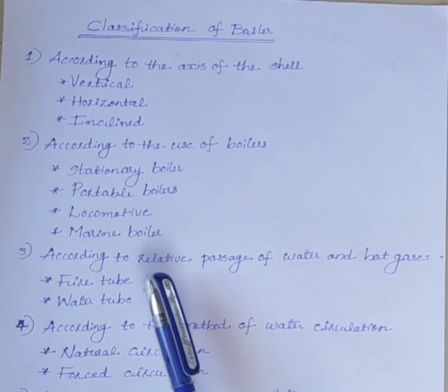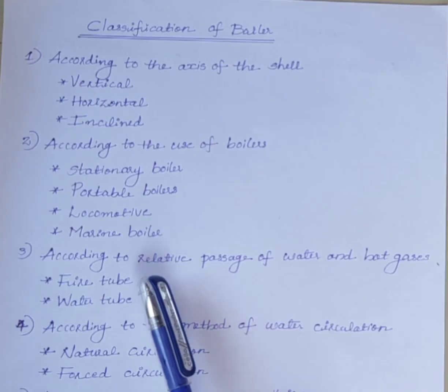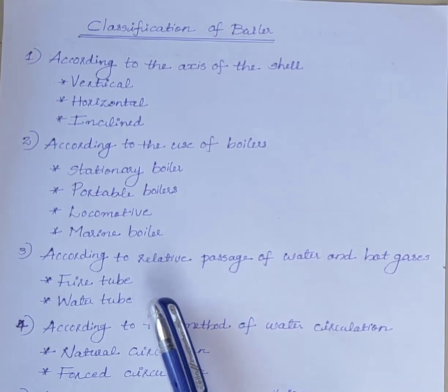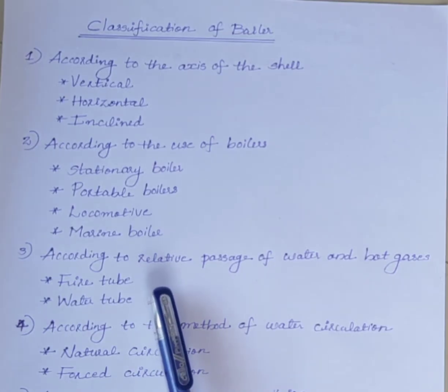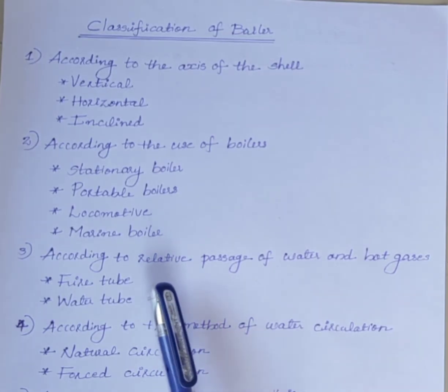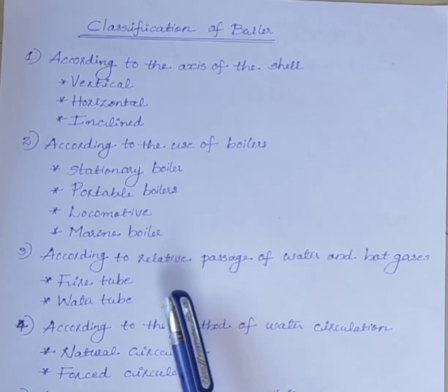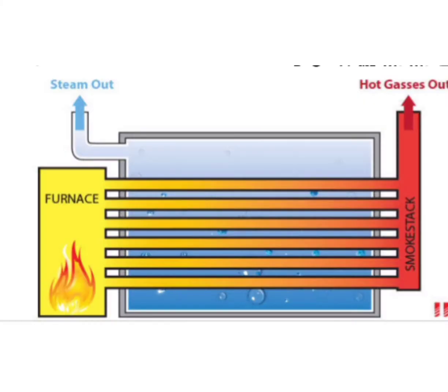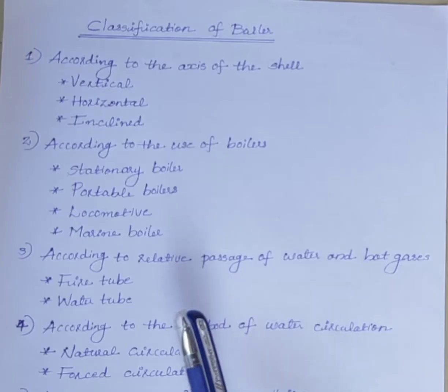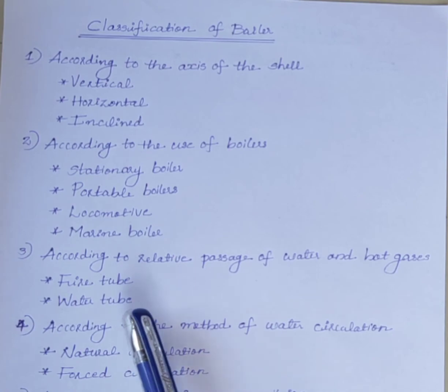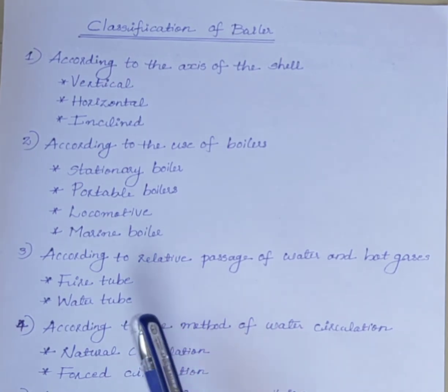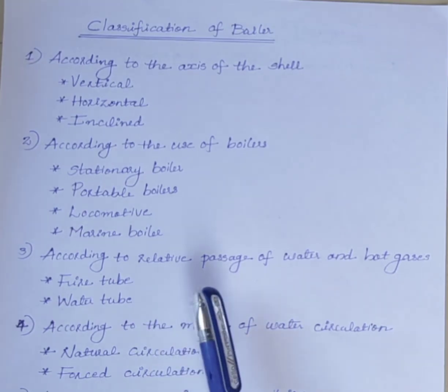The next classification is according to the relative passage of water and hot gases. There are two types: fire tube and water tube. In fire tube boilers, the hot gases are inside the tubes and the water surrounds the tube. In water tube boilers, the water is inside the tube and hot gases surround them.